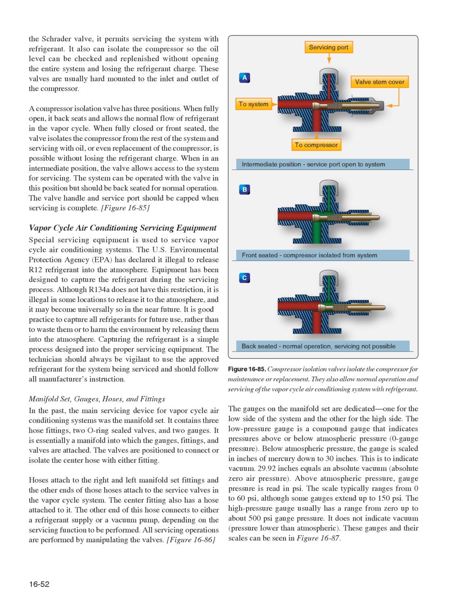It is good practice to capture all refrigerants for future use, rather than to waste them or to harm the environment by releasing them into the atmosphere. Capturing the refrigerant is a simple process designed into the proper servicing equipment. The technician should always be vigilant to use the approved refrigerant for the system being serviced, and should follow all manufacturer's instructions. Manifold set, gauges, hoses, and fittings.